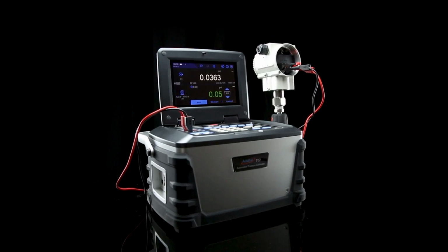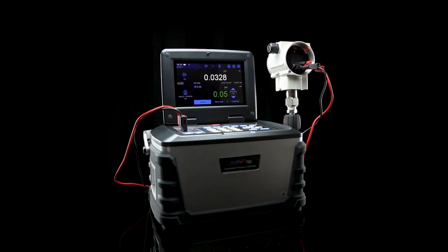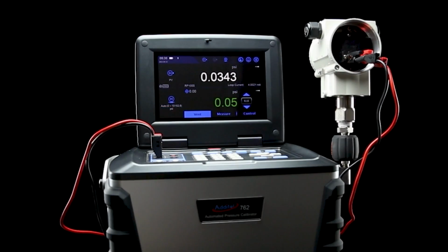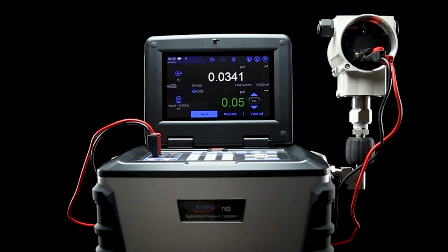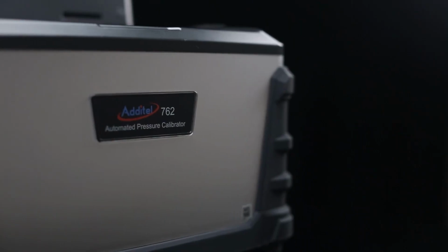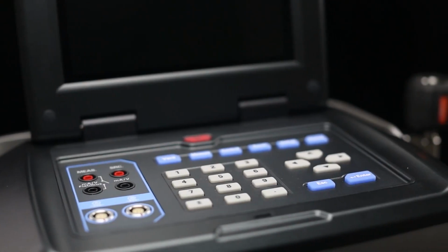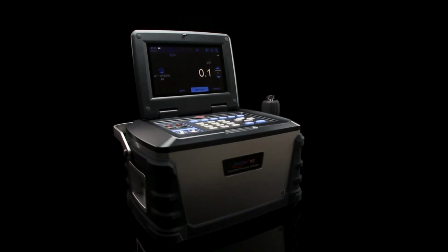We hope you enjoyed this demonstration of the 762's calibration process. With multiple device test options, HART communication, and a built-in data converter, the 762 is the ultimate tool when you need to perform efficient calibrations up to 10,000 psi.